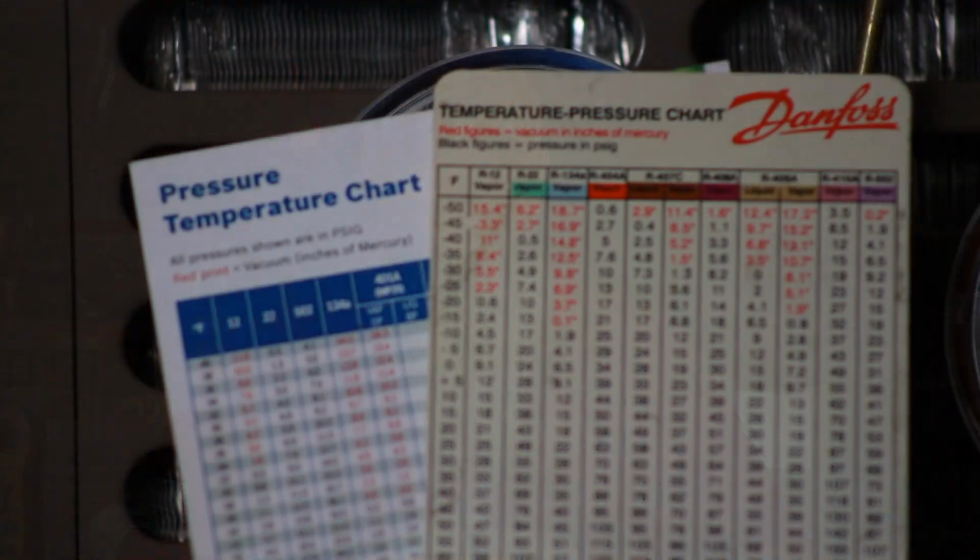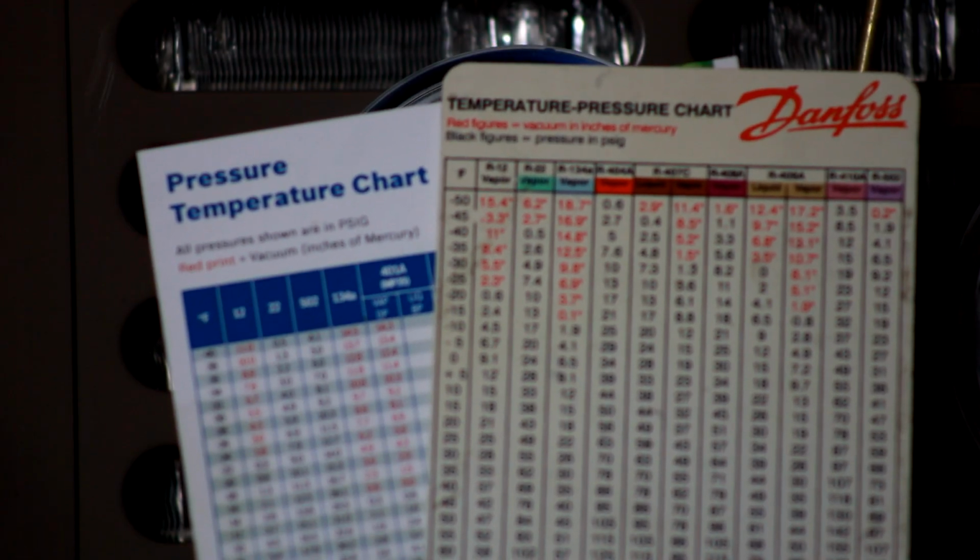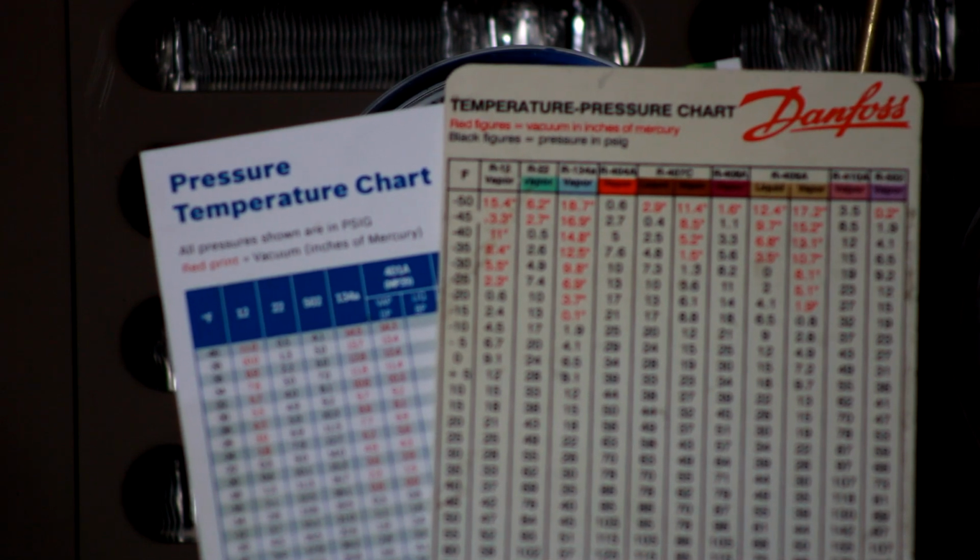This is important to understand because when refrigerant is gaining latent heat, it's changing state. And once in the evaporator side, since we're talking about superheat, once it completely changes to vapor, it is classified as saturated. That's its saturation point. And so any sensible heat that we gain above that saturation point is our superheat number.